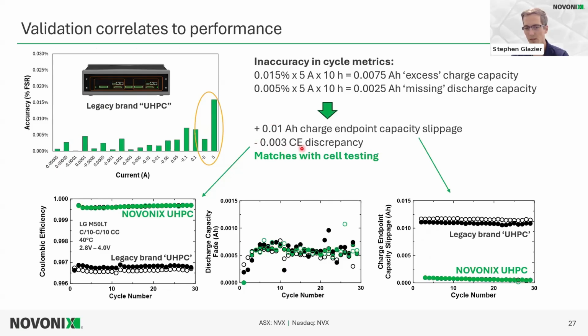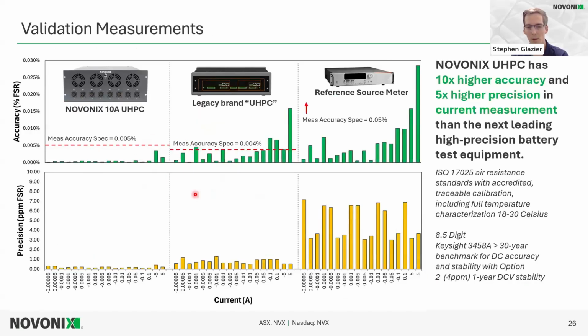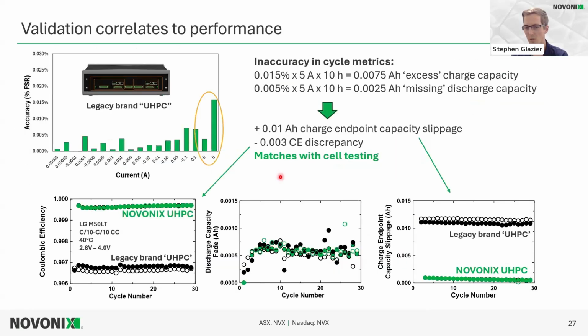And then we expect to see a discrepancy of about 0.003 in coulombic efficiency just from this mismatch, which also translated almost perfectly to the performance that we measured in the cells, along with a little bit of issues with precision and repeatability of the measurement. But this just goes to show that these measurements really matter, especially when looking at cell-to-cell variation or differences in electrochemistry. So I just wanted to bring it back to cell testing for a minute, and I'll pass it back to Mike to wrap up the hardware design discussion.